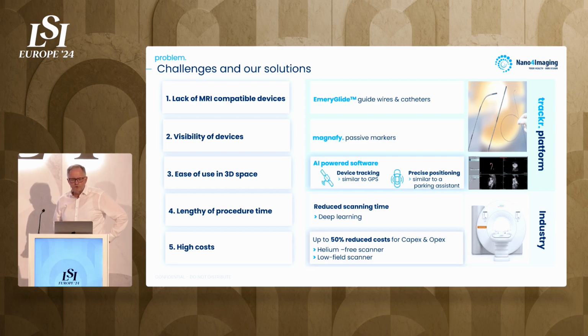However, there are a few challenges to overcome. First, devices containing metal cannot be used in MRI. Therefore, we have developed EmeryGlide, the first available non-metallic guide wire. Second, our Magnify MR markers, which are nanocoatings, make devices in the MRI visible. Third, the software algorithms recognize MR markers and allow the tracking and positioning of devices, like a GPS or a parking assistant.